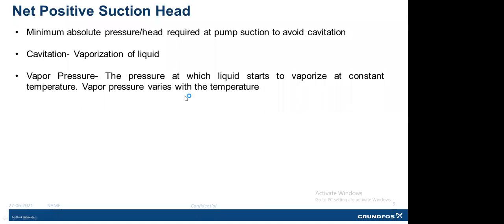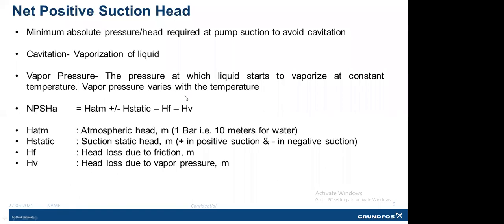So how do we calculate the NPSH available at site? There is a formula. It is calculated by atmospheric head plus or minus static head. We will add the static head if it is a positive suction, and we will deduct the static head if it is a negative suction, minus HF.